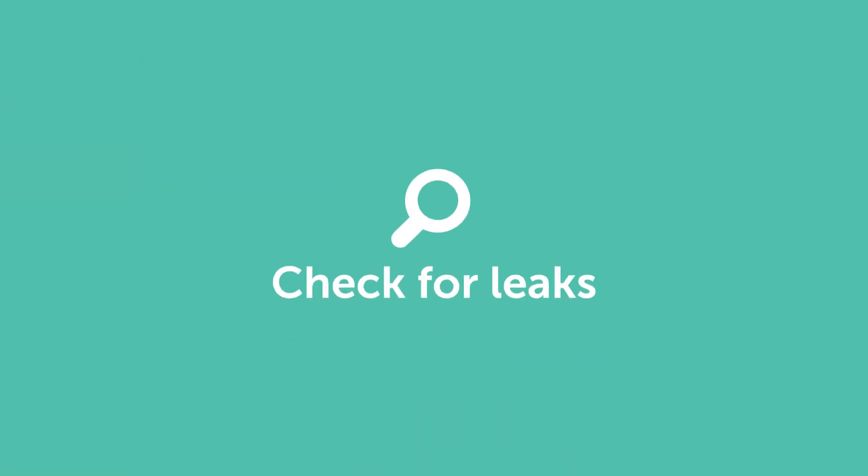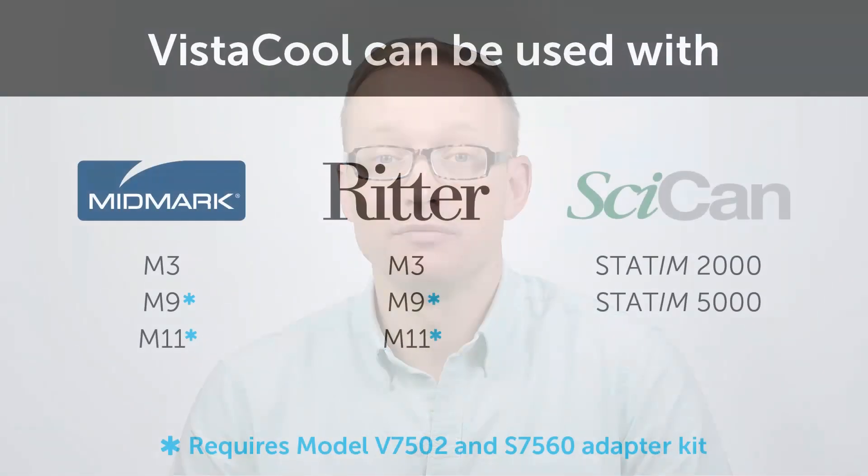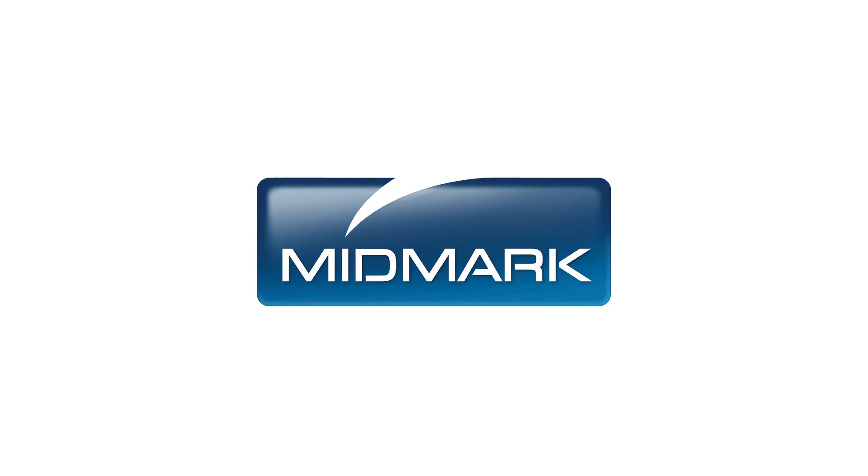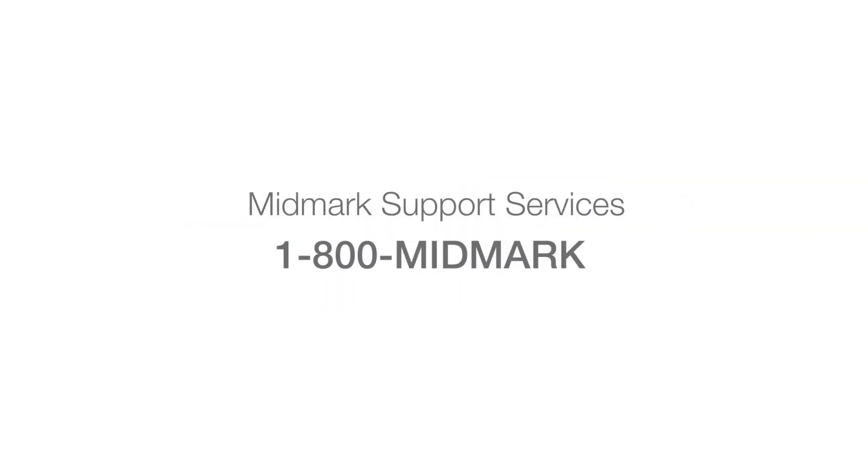Check again for leaks, then run three consecutive autoclave cycles to ensure everything is working properly. Once VistaCool is properly installed, it will function without operator input. Beyond periodic visual inspections of the tubing, there is nothing users must do to ensure proper operation. For more information, contact Midmark Support Services at 1-800-MIDMARK.